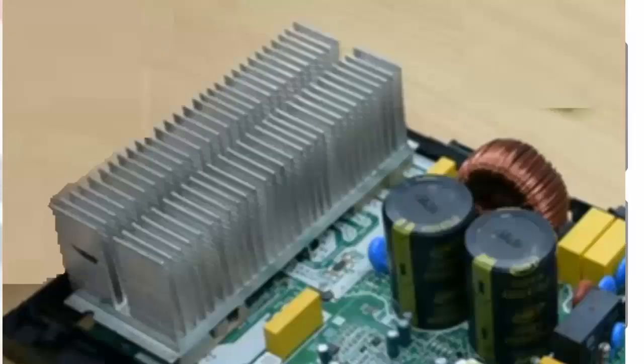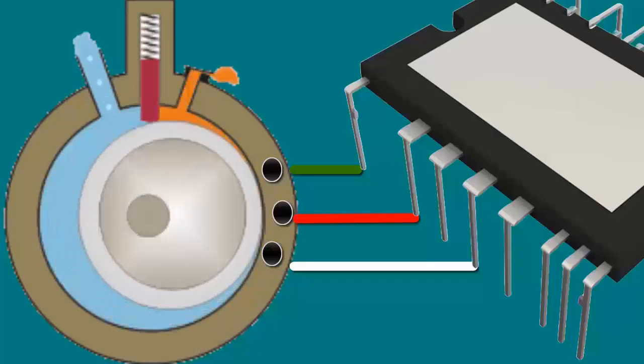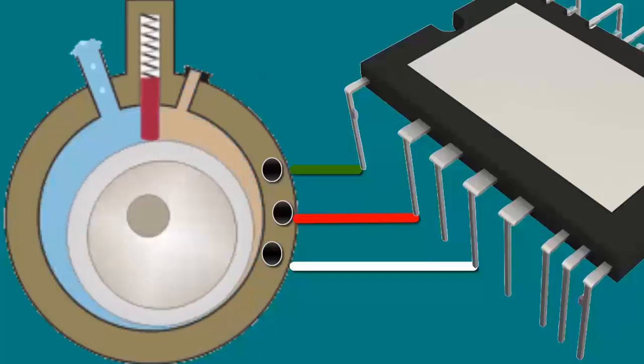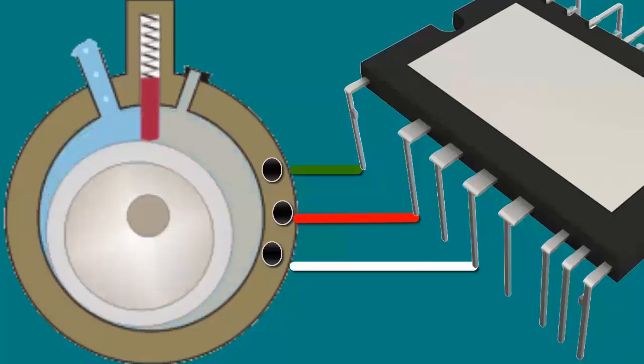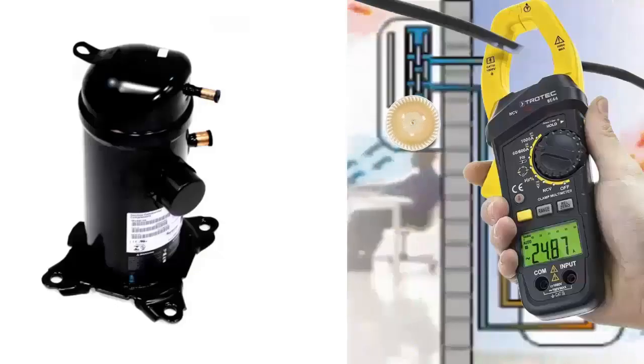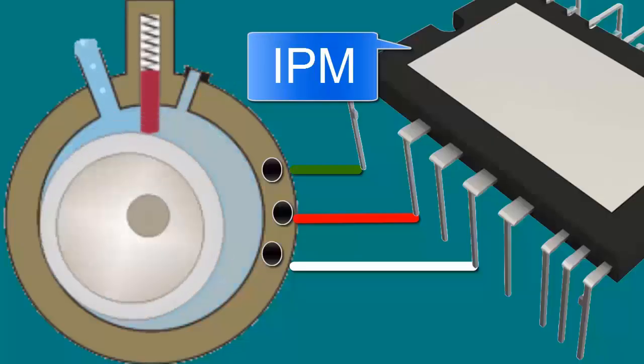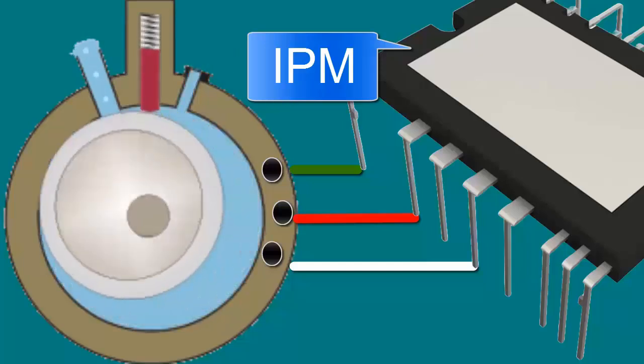6. Check the continuity in the tracks of the external electronic board from the IPM electronic module to the compressor cable outlet. 7. If the system manages to start, check the voltage supply at the IPM module output pins and its ground.